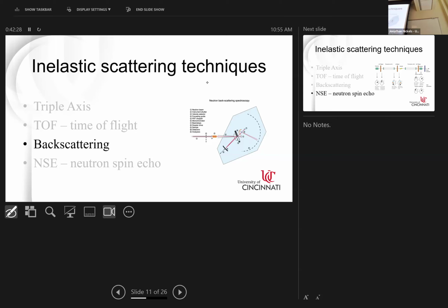And what it does is it takes the velocity encoding out of a physical clocking, and it puts the velocity encoding in the wavelength that's reflected. So only the wavelengths that are reflected are what you see in your signal. And that's a way of just cheating the clock, right? Because it doesn't matter what you see, you still have a clock. The resolution isn't that electronic clocking, it's the reflections off this crystal giving you a new spectrum in time.